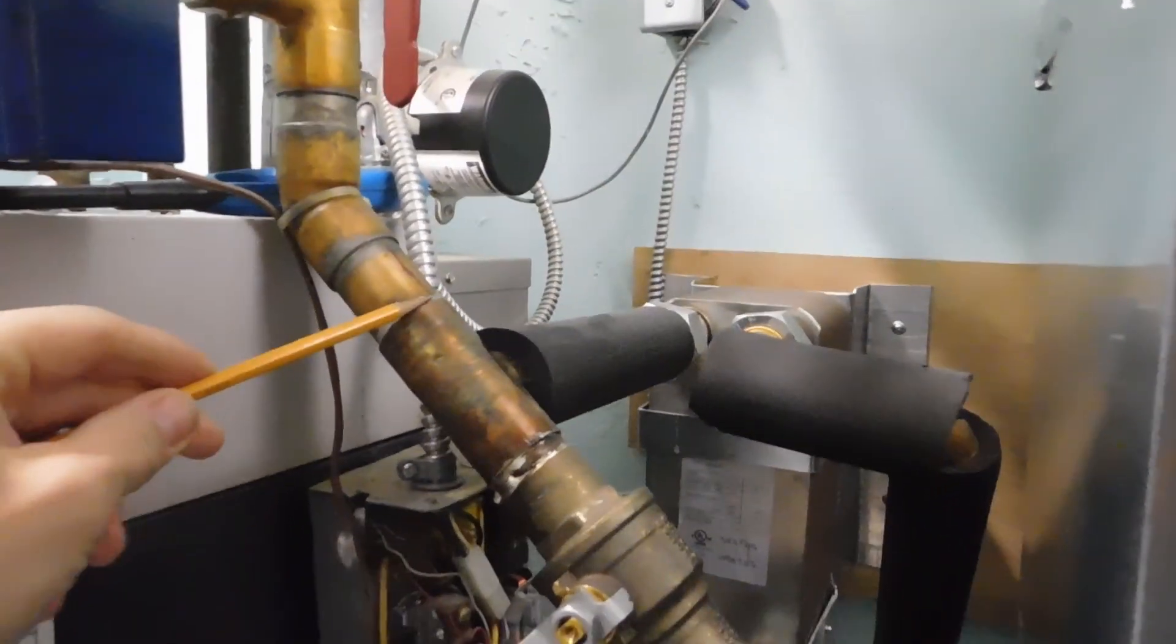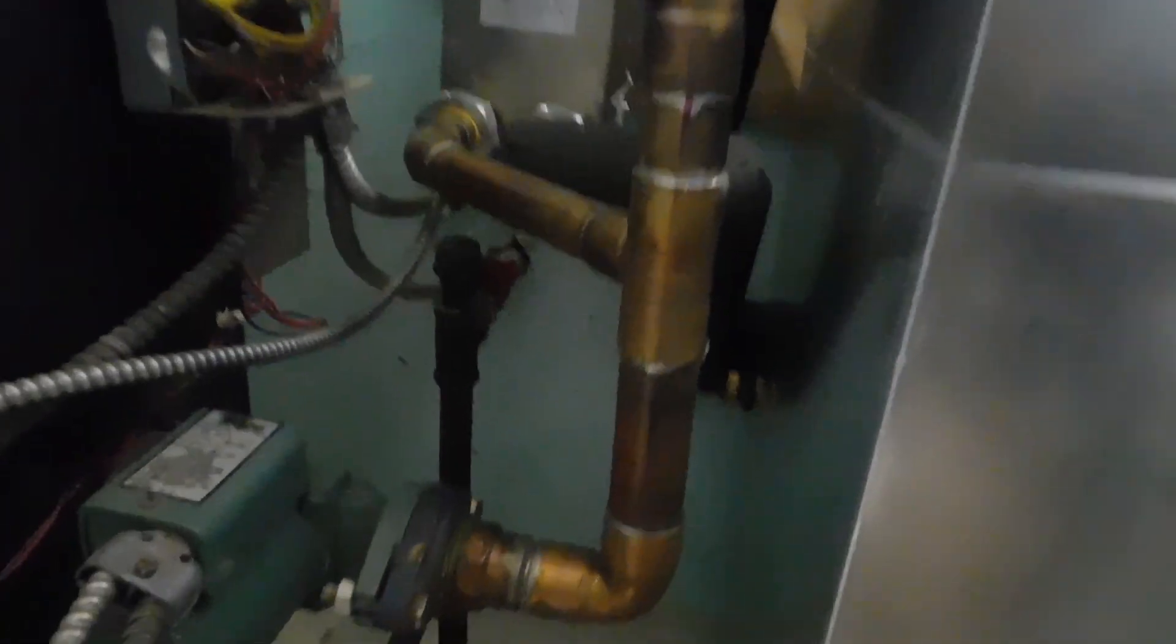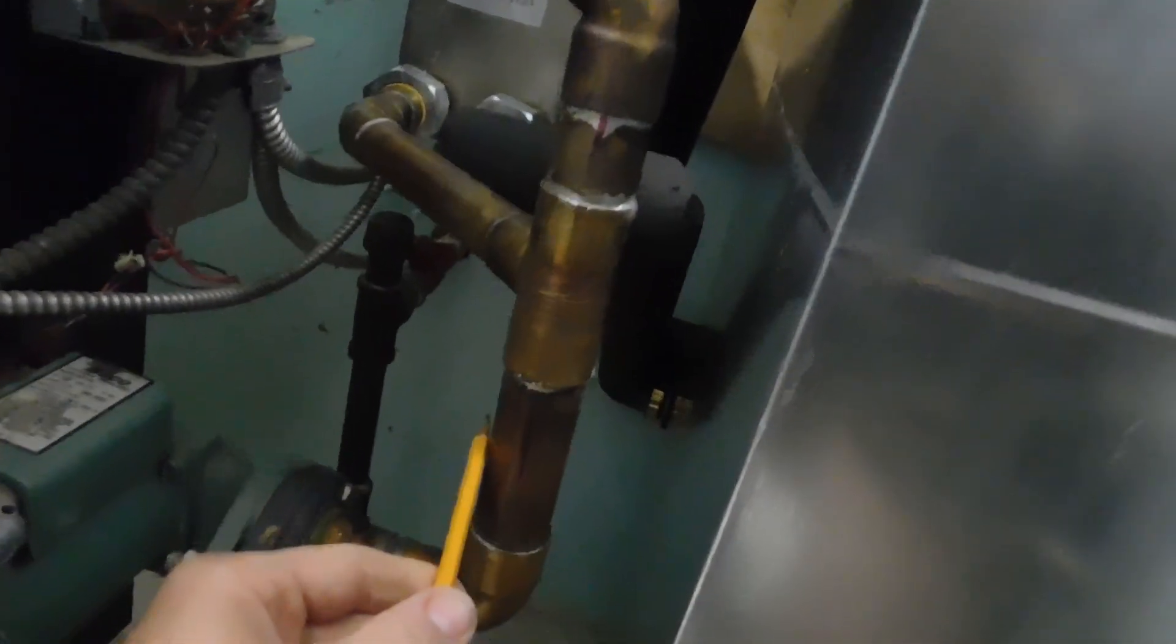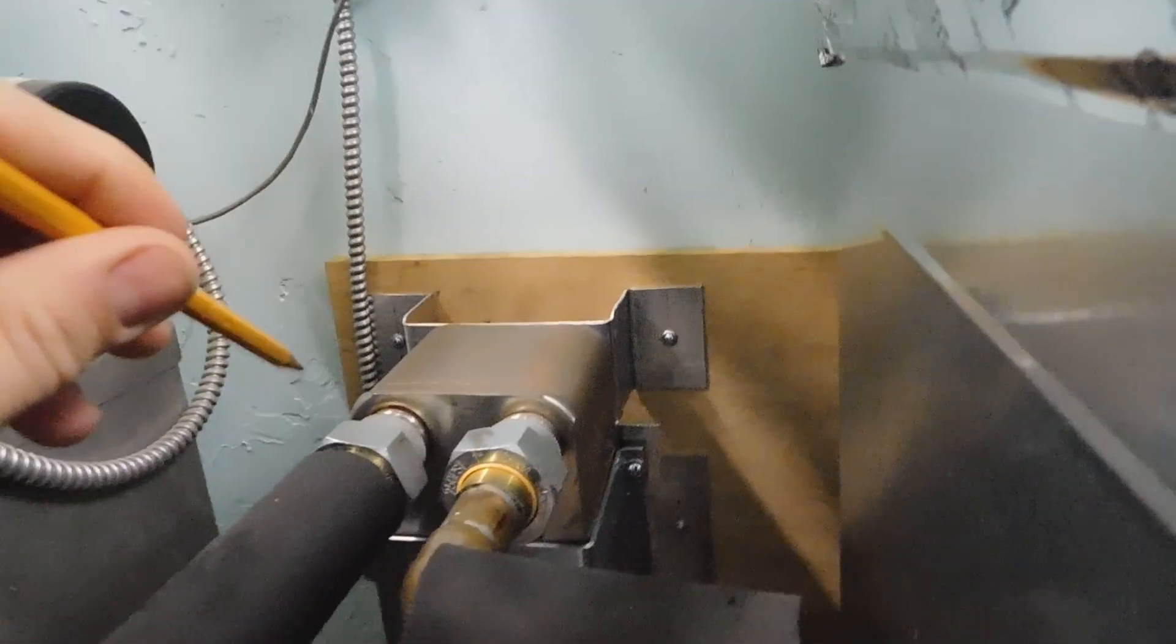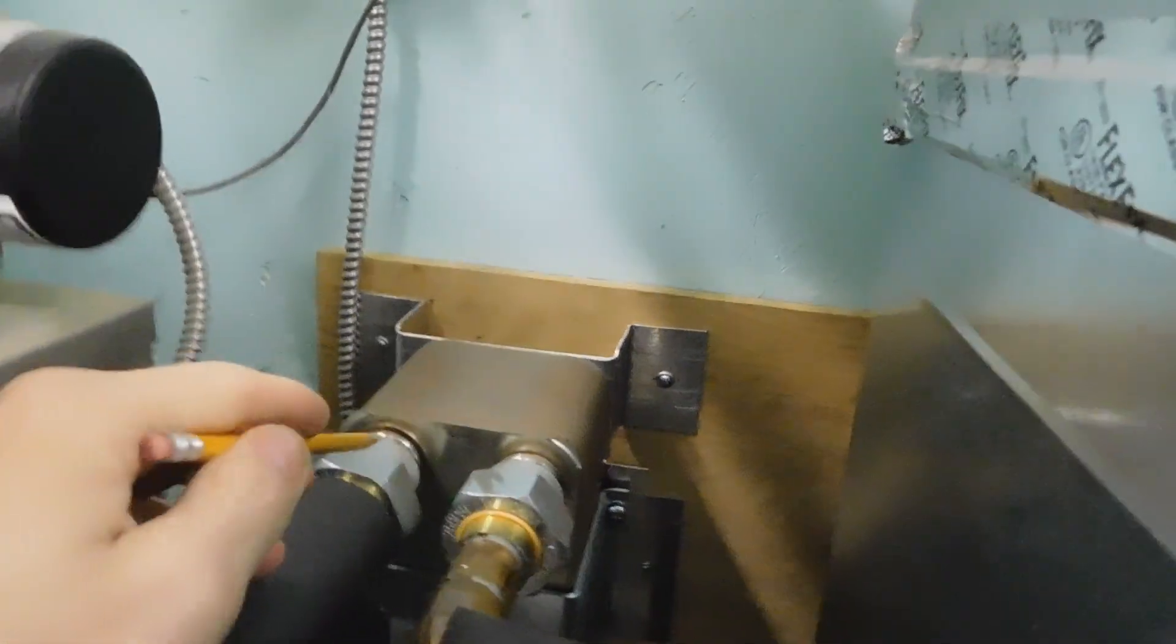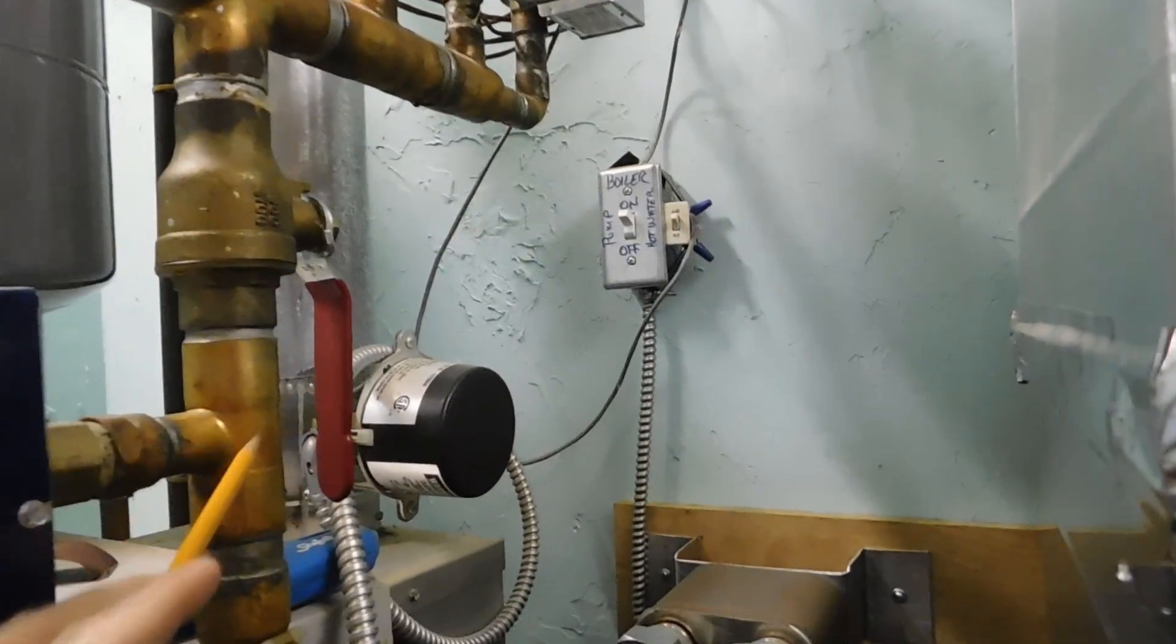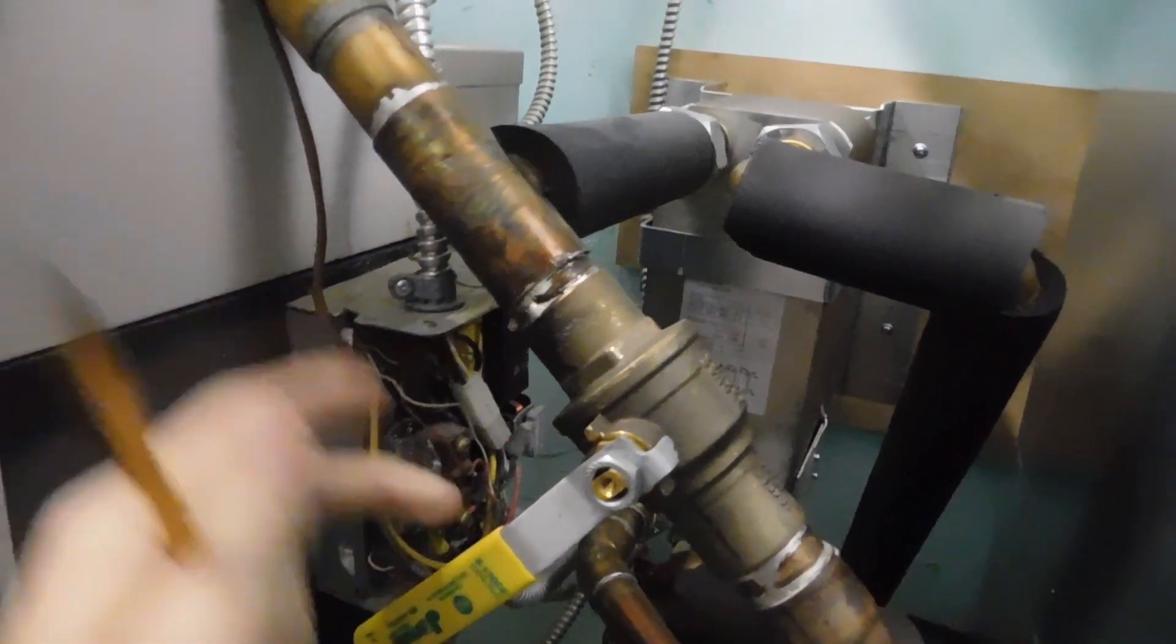I cut it up here, I cut it down here so that I could get a T in under this insulation. So I could get a T in here, alright. So this is all inch-and-a-quarter, and then I pumped one inch. So inch-and-a-quarter down to a one-inch T, because the plate exchanger is one-inch NPT. So dielectric couplers with high-temp gaskets in them.